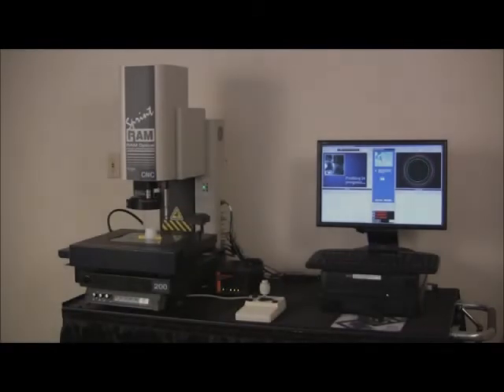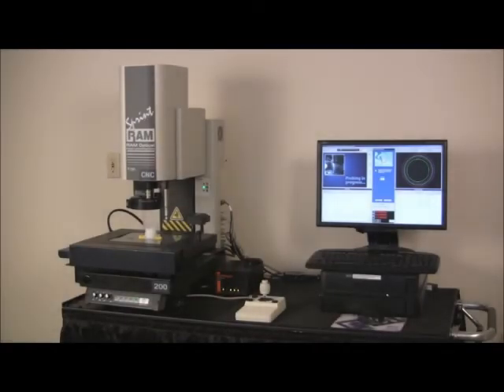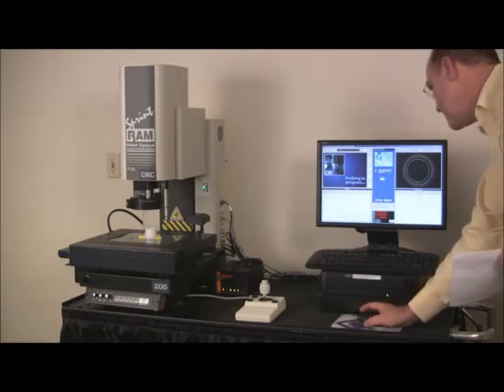Okay, what we've done, I removed the bottle in the horizontal position and I cut the neck off one of the other bottles. This machine only has 6 inches of travel in the z-axis, and the length of the bottle was 9.15. So certainly we couldn't measure it standing up. Now we do have machines with a 12-inch z-axis where we could accommodate the bottle as it sits. But what we're doing now is we're going to measure the ID of the bottle using the video, and then we'll use the touch probe to measure the 3 diameters that require the 6-point measurements for roundness.